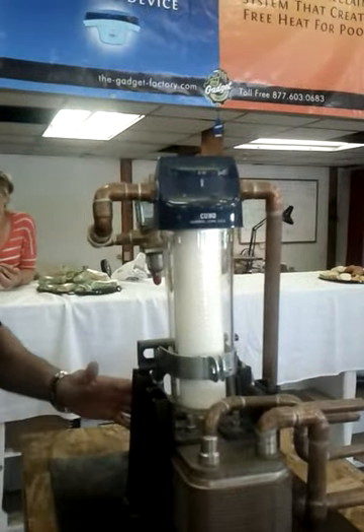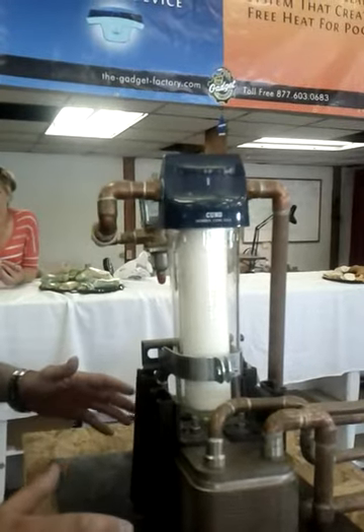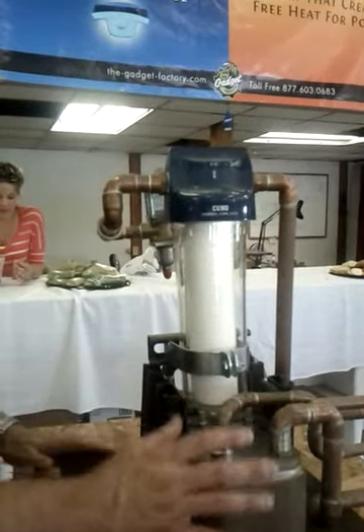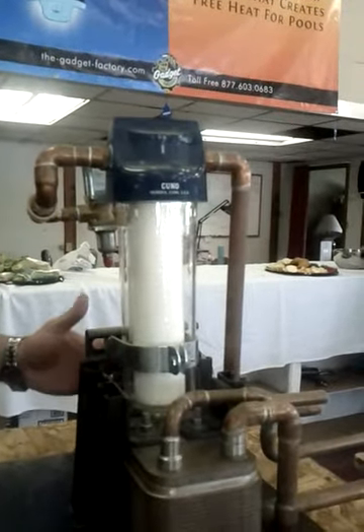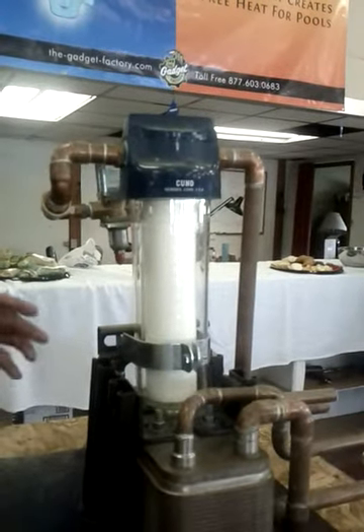But this was where I originally designed the heat sheet system, was for swimming pools, and the same thing goes here. We cool the gas from the AC unit, send it back cooled with the pool water. The end result is that we get 140 degree water at a rate of about 8 gallons per minute that mixes in with the rest of the filtration. Now, we've had one in service for over 3 years, and it provides for a 35,000 gallon swimming pool. We're able to maintain mid-80s with regular AC use, saving our customer in the neighborhood of $300 a month. This system installs for right around $4,000 and has an ROI of typically 3 years or less. And that's how it started.